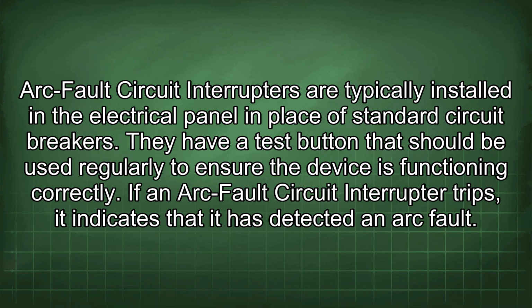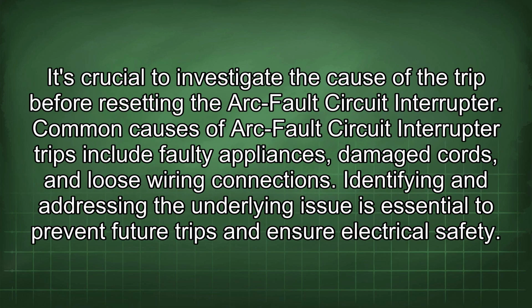If an arc fault circuit interrupter trips, it indicates that it has detected an arc fault. It's crucial to investigate the cause of the trip before resetting the arc fault circuit interrupter. Common causes of trips include faulty appliances, damaged cords, and loose wiring connections. Identifying and addressing the underlying issue is essential to prevent future trips and ensure electrical safety.